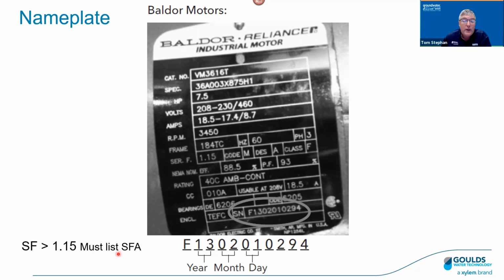You don't have to list it. But if it's greater than 1.15, you must list the service factor amps. So this is an example where just because the motor does not show service factor amps does not mean that they're not there. The other important thing here, there's lots of other stuff. Look at this, usable at 208. That confirms that we can use this at 208 supply voltage.